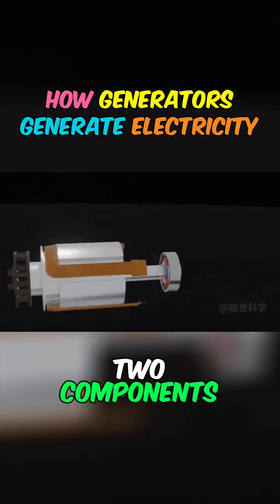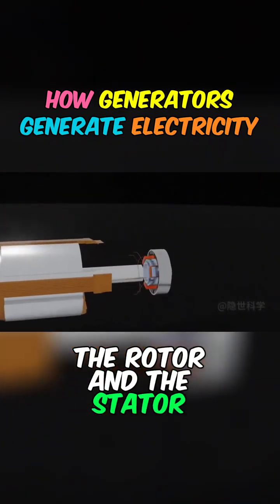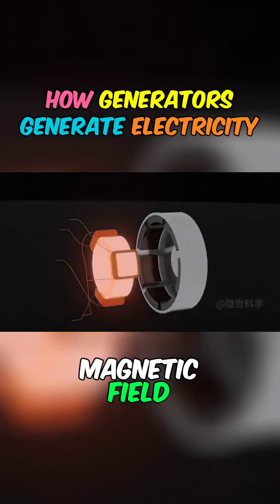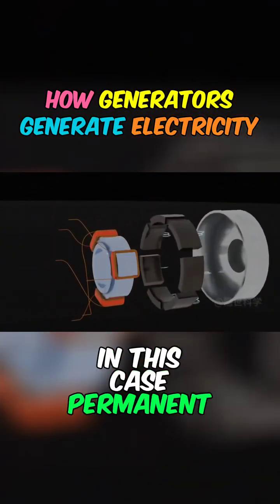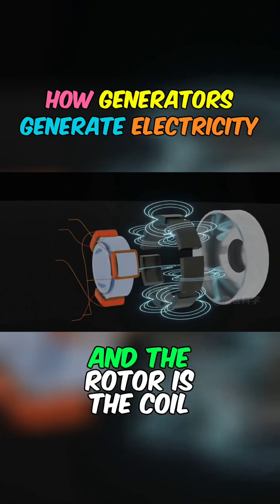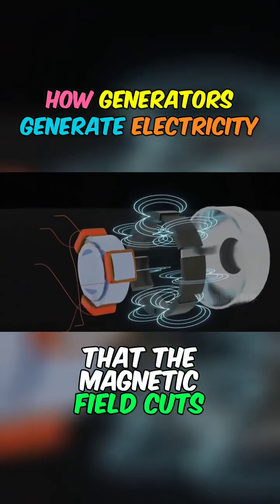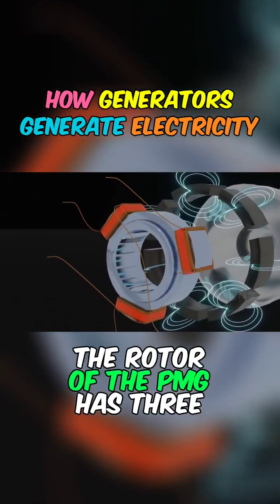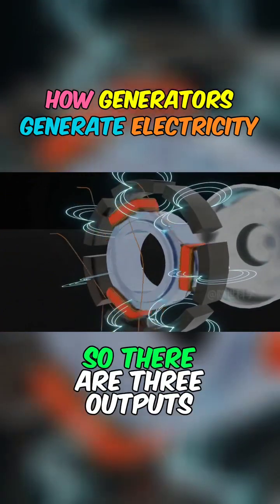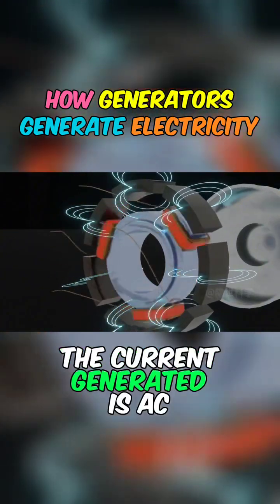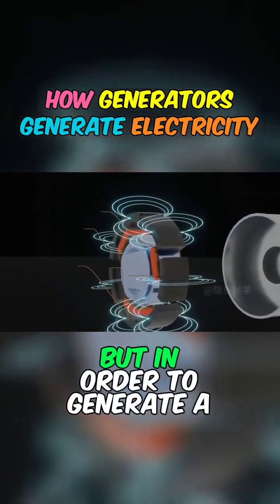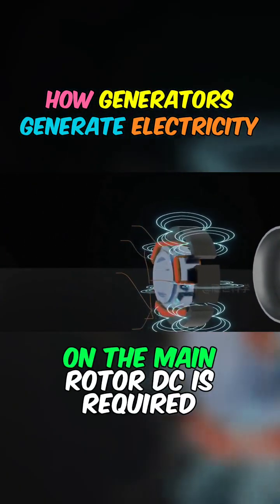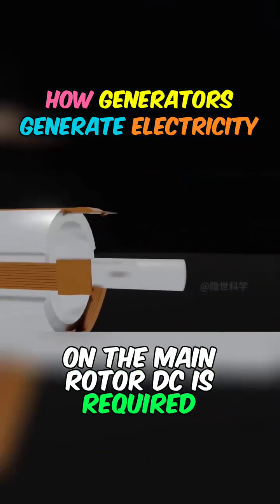The working principle is almost the same as a general generator. There are two components, the rotor and the stator. The stator provides the magnetic field. In this case, permanent magnets are used, and the rotor is the coil that the magnetic field cuts. The rotor of the PMG has three coils, so there are three outputs. The current generated is AC, but in order to generate a magnetic field on the main rotor, DC is required.